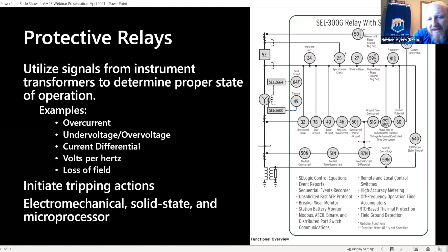If, for example, we were to see an overcurrent situation occur, the relay itself would pick up a contact and initiate a tripping action. Within Reclamation, we still have electromechanical and solid-state relays, as well as these microprocessor-based relays. If we utilize electromechanical and solid-state relays, we tend to have one relay box for every one of these protective elements. However, by going to a microprocessor-based relay, we can incorporate what might have been 20 to 30 electromechanical relays into one box.